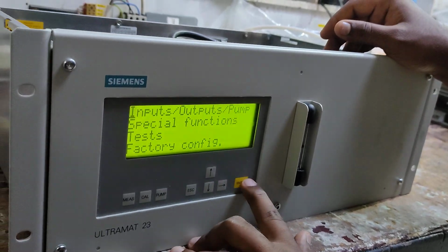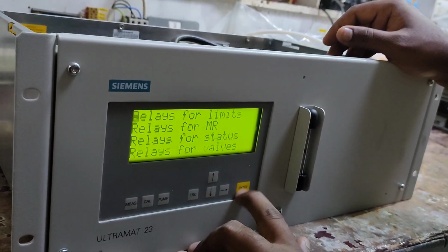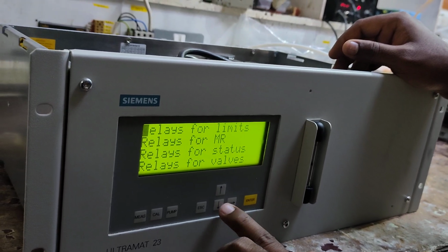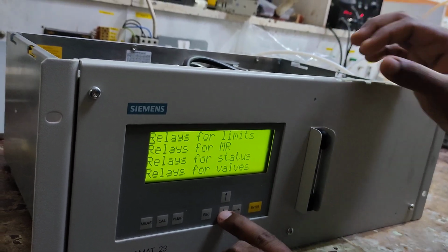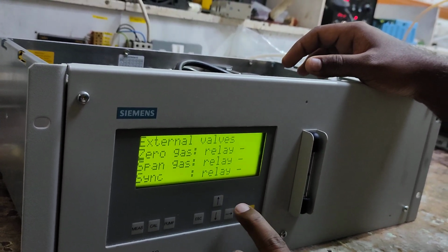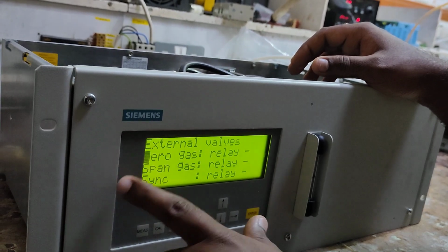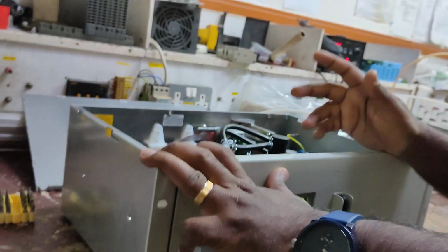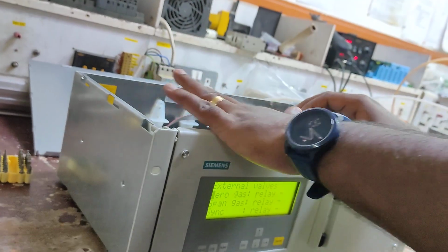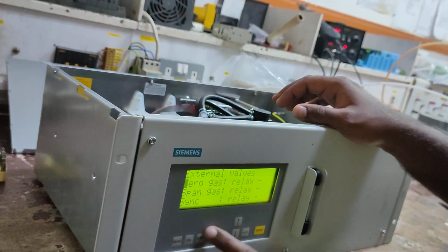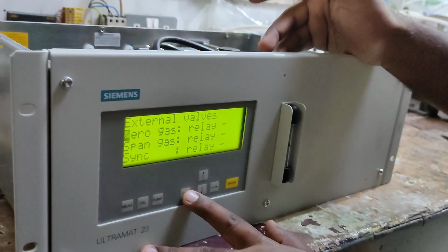Similarly, for configuration we will go to assign relays. If you want to actuate any valve, you go to the valve and then select the relay. For zero gas, you can select one relay. For span gas, you can select another. But that cable from the back side, you have to take and connect it also. If it is not connected, it will give the command only, but it will not have any actuation. But if you are doing it manually, then there is no need of all this.